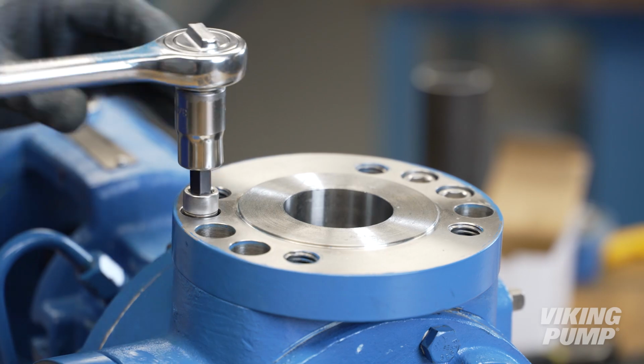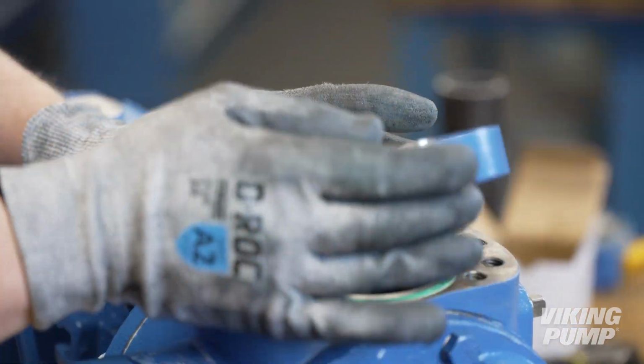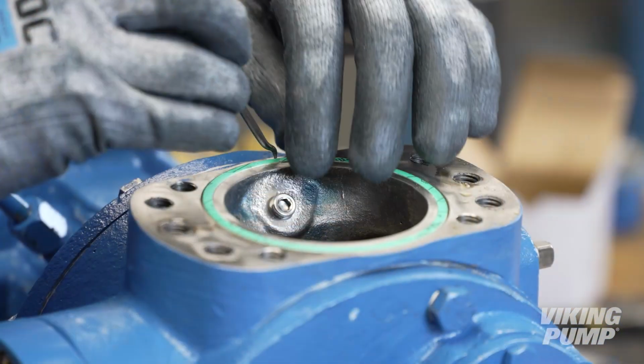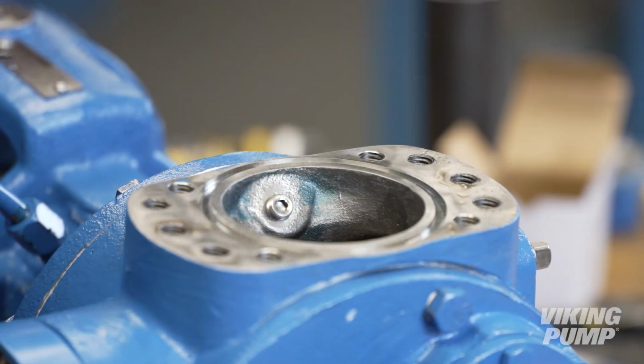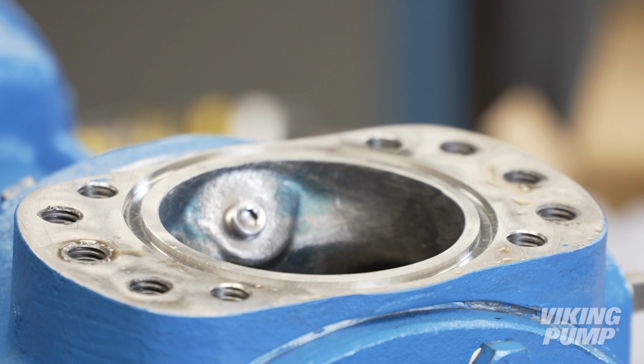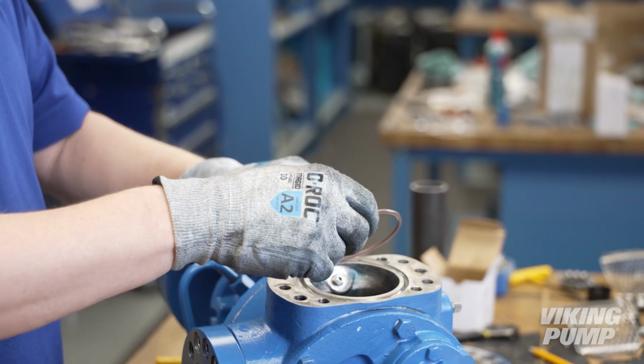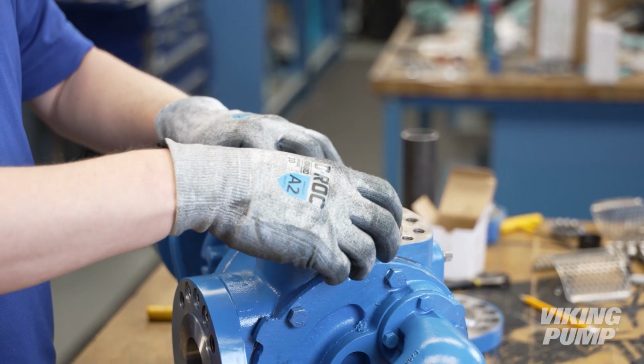When the pump is reassembled, you can swap elastomers between the ports and casing as well. Remove the flanges and discard the gasket or O-ring from the casing. Ensure the sealing surfaces near the casing ports are clean and free of debris. Install an O-ring or gasket into the groove on the casing.